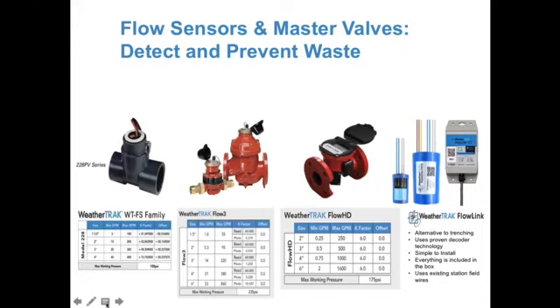In addition to an irrigation control system, the benefit of putting a flow sensing device in line with the irrigation main line allows you to monitor the flow of water, learn flow for a main line, learn flow for station lines, and then be able to set thresholds for when those lines or main lines are broken. And so it will eliminate the catastrophic event of a mainline break or the continuous leak on a valve or a broken head. And the benefit of this is to help you capture and retain all the savings you generated by putting in a weather-based control in the first place.